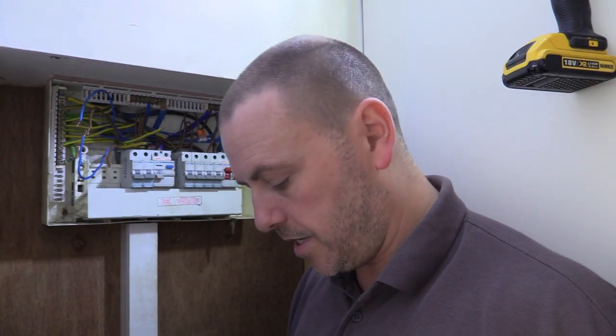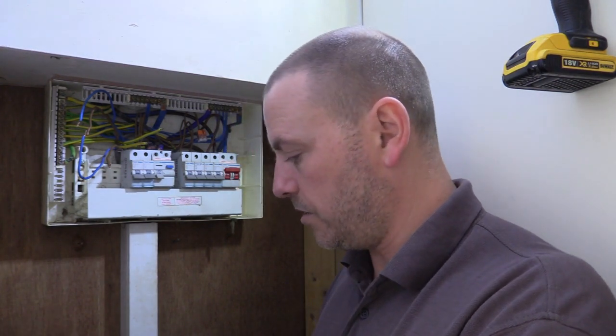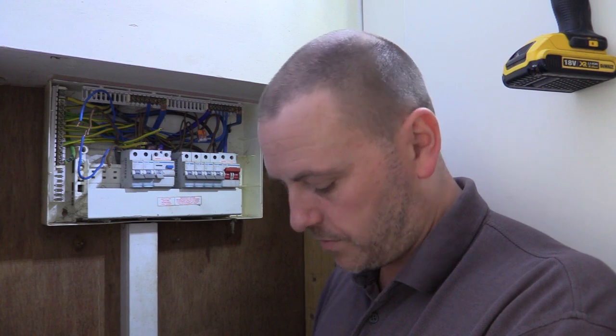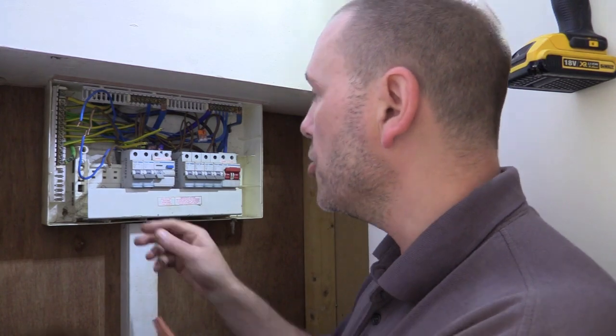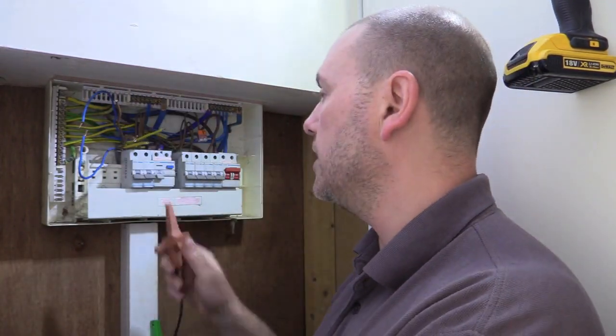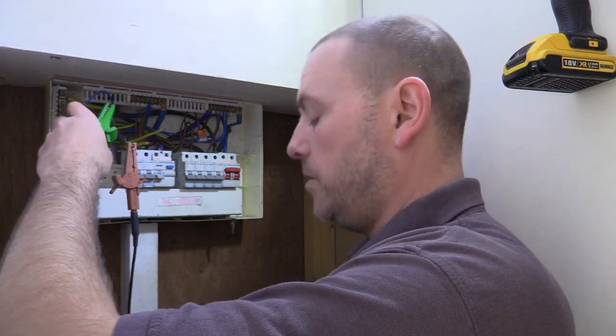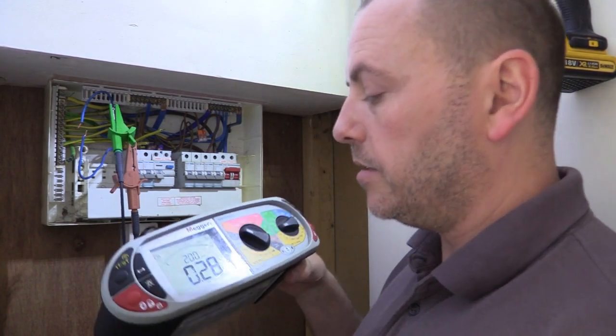So, ring testing. First thing, zero the leads. Done. We're going to do continuity of each ring, so live to live, write it down, neutral to neutral, write it down, CPC to CPC, write it down. So, there's my two live legs, one on there, one on there.